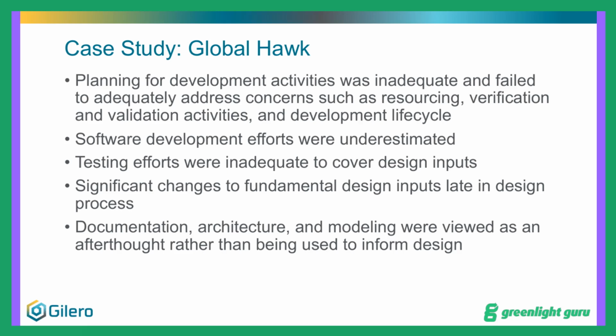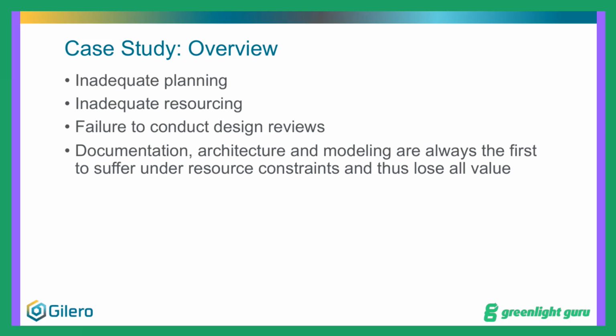Ultimately, due to failure to plan and failure to conduct design reviews, testing efforts were insufficient to provide full coverage of all design inputs. This was compounded by significant changes to fundamental design inputs late in the design process, such as a 50% increase in required payload capacity. Because the project was under-resourced, using development life cycles inappropriately, and facing significant changes throughout the design process, as is typical, the first things to go were design control elements, like documentation, architecture, and modeling. These were all slapped together towards the end of the project as a checkbox compliance activity instead of using them to inform the design process. What patterns can we identify from the previous two case studies?